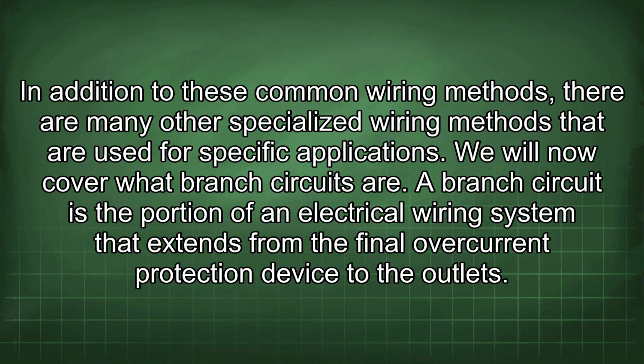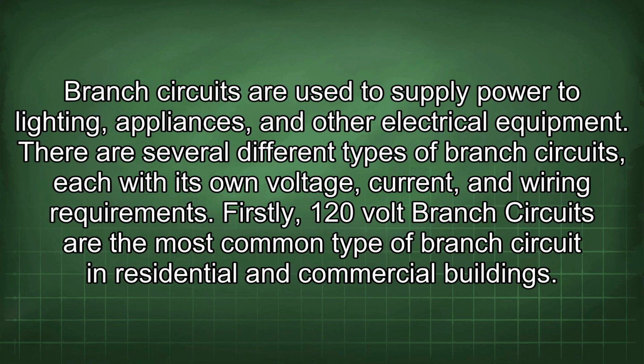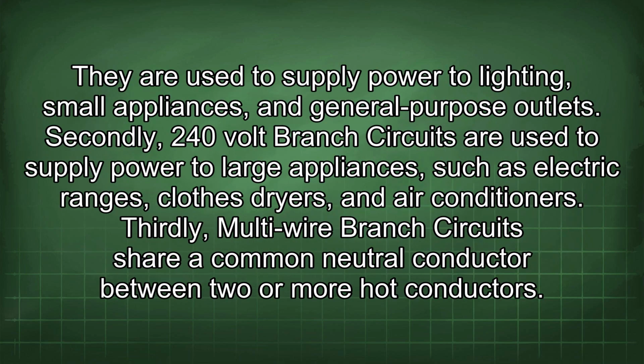We will now cover what branch circuits are. A branch circuit is the portion of an electrical wiring system that extends from the final overcurrent protection device to the outlets. Branch circuits are used to supply power to lighting, appliances, and other electrical equipment. There are several different types of branch circuits, each with its own voltage, current, and wiring requirements. Firstly, 120-volt branch circuits are the most common type of branch circuit in residential and commercial buildings. They are used to supply power to lighting, small appliances, and general-purpose outlets.